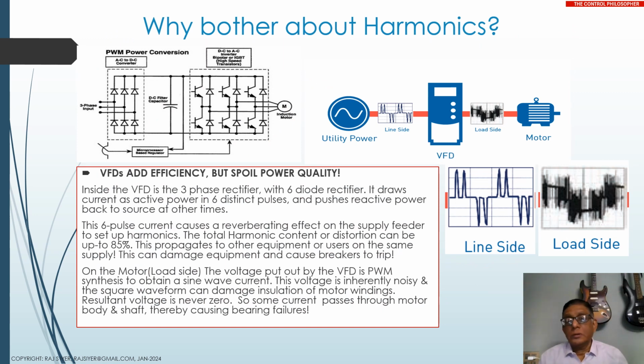See, there are two kinds of harmonics actually. One is on the line side, that is on the line that is supplying power to the VFD. This is caused by the rectifier side. Because the rectifiers are arranged as a six-pulse, three-phase full wave configuration, they draw active power in six distinct pulses, and this has the potential to push back reactive power into the line that feeds. This is due to reverberation on the supply feeder. If we don't take enough precaution, this harmonic distortion can be up to even 85%.